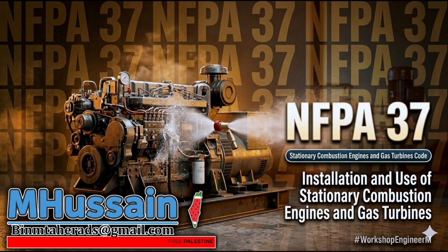Much heavier. If a propane line leaks indoors, the gas cascades down the side of the engine and pools on the floor. Like invisible water filling up the room. Exactly. It settles into trenches and drains, creating a highly explosive mixture just waiting for a single spark. Which is why indoor propane engines mandate low-level gas detection. Yes, sensors mounted right near the floor. It's a specific requirement for heavier-than-air fuels.